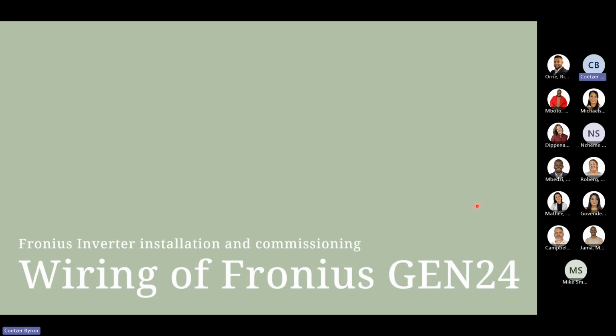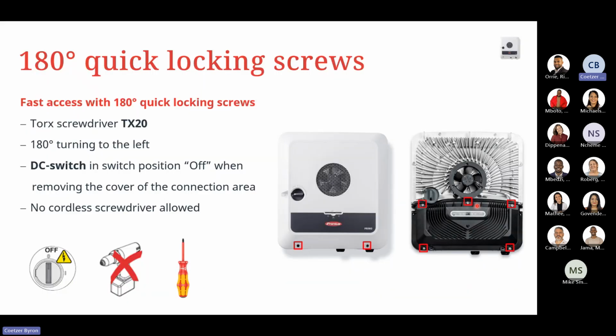So the wiring of the Fronius Gen 24. You have to use a Torx 20 screwdriver, and that is all that's required when doing the installation and commissioning process for the Gen 24. So we'll use our Torx 20 screwdriver. We'll then remove the inverter cover. So it's two simple screws here on the bottom of the unit. You turn them 180 degrees to the left to loosen.